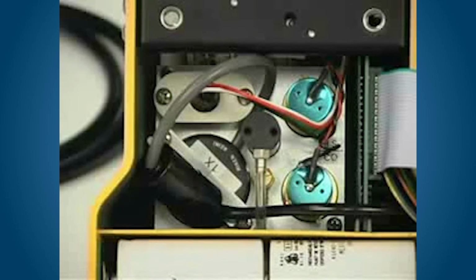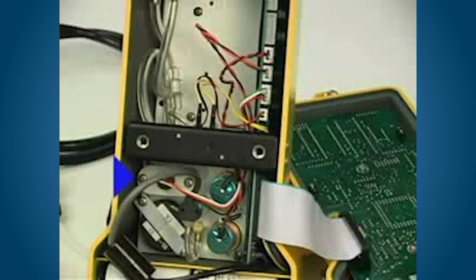The standard 4-gas Eagle is equipped with 4 sensors to monitor combustibles, oxygen, carbon monoxide, and hydrogen sulfide. These standard sensors have an operating life of approximately 2 years. The combustible sensor is mounted with a flame arrestor down in the sensor block to allow the sample flow to diffuse into the sensor. The sensor cable connects to the pins on one end and terminates in a 4-position connector, which plugs into the COMB, or combustible socket, on the analog print circuit board.